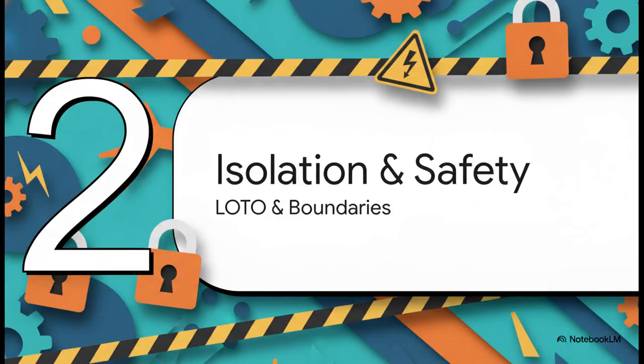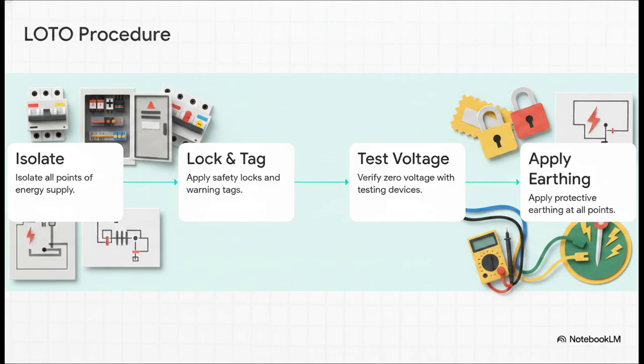Moving right along to phase 2, isolation and worksite safety. This is all about lockout/tagout and approach boundaries. This sequence is rigid, unbending, and completely non-negotiable. It's your audit-ready lockout/tagout procedure to make sure a system is totally de-energized. First, isolate all supply points, period. Second, put on your safety locks and warning tags right at that primary energy source. Third, you have to use an approved voltage tester to verify zero voltage. That's your mandatory test before touch protocol. And finally, you apply protective earthing at every disconnection point. Why? To bleed off any of those nasty induced or capacitive voltages that might be lingering.